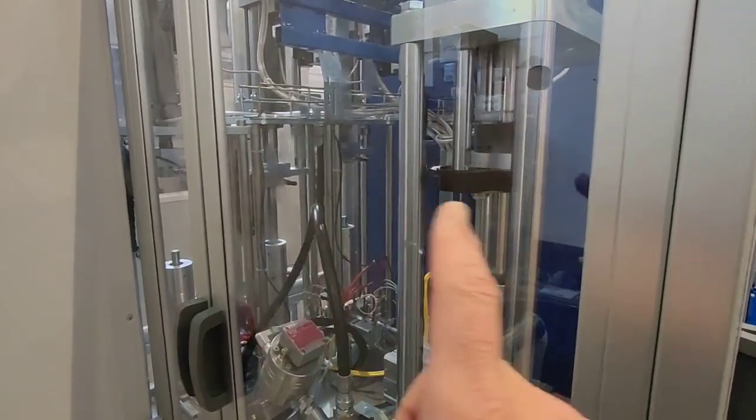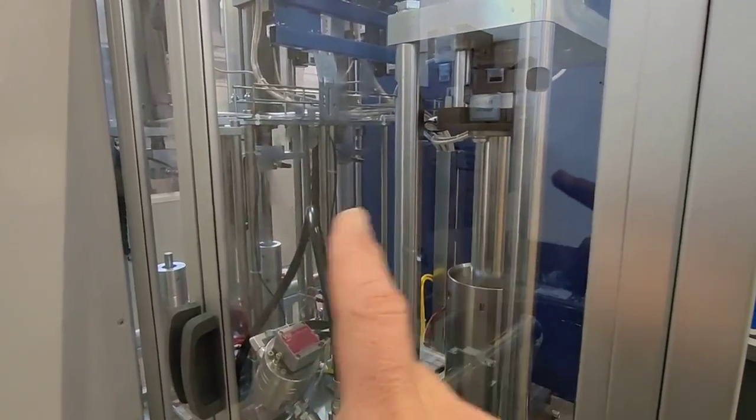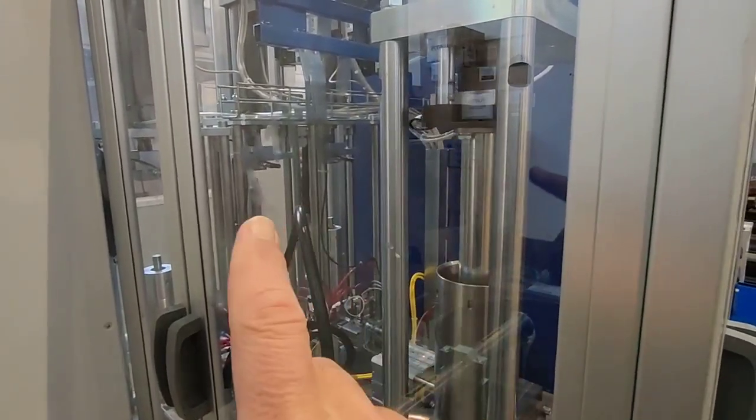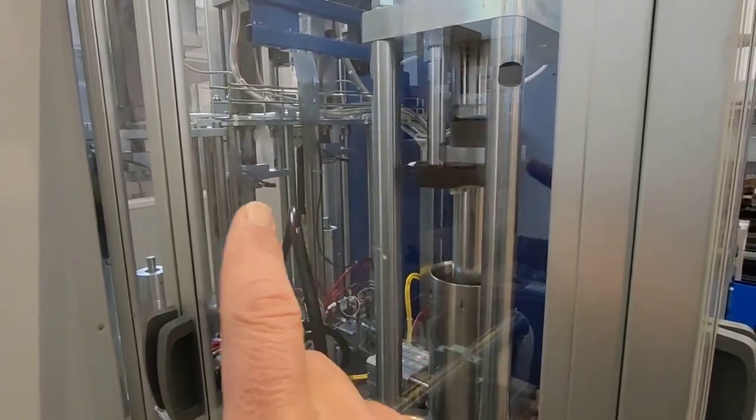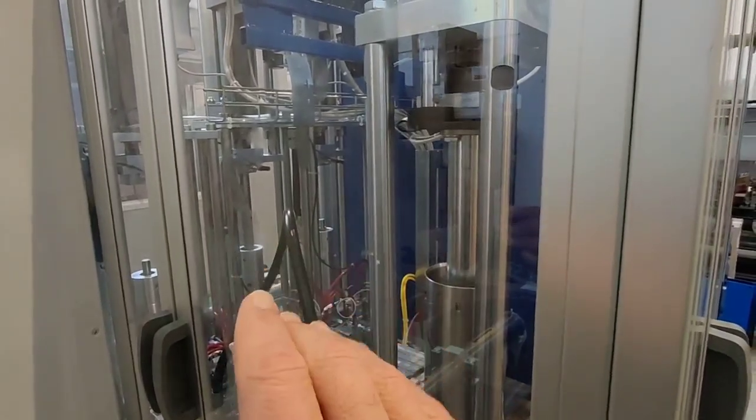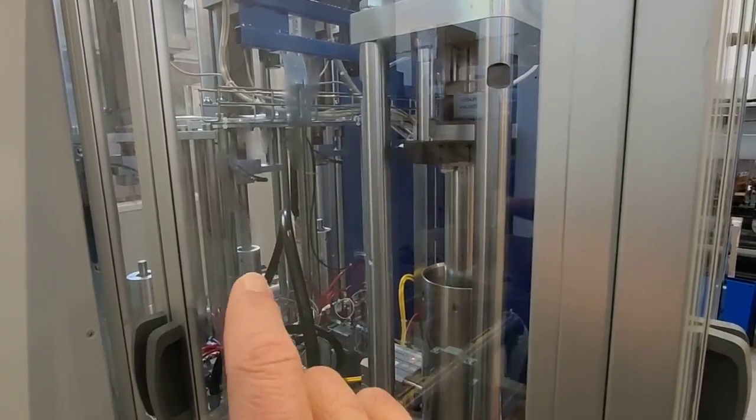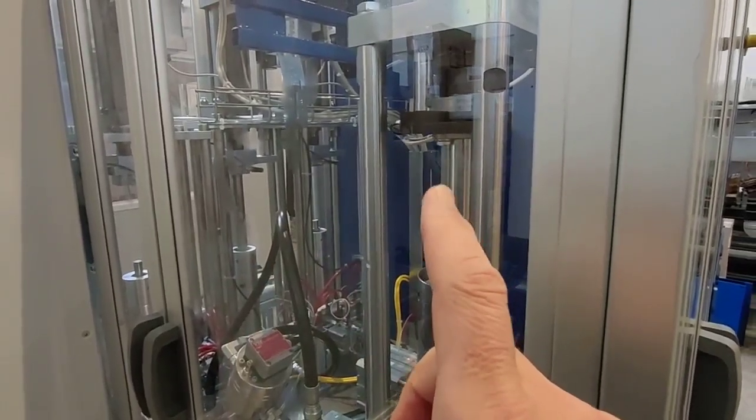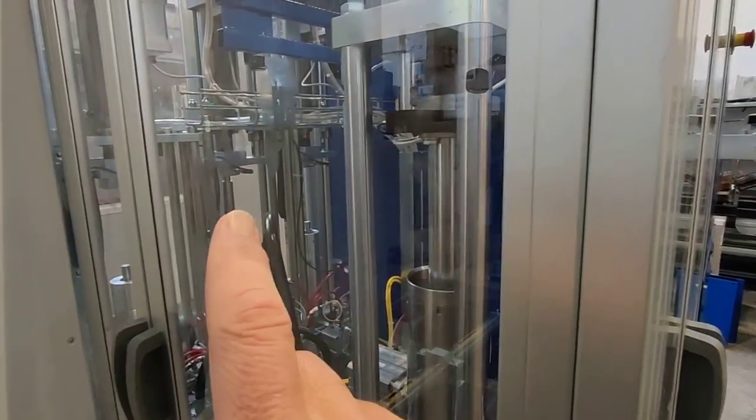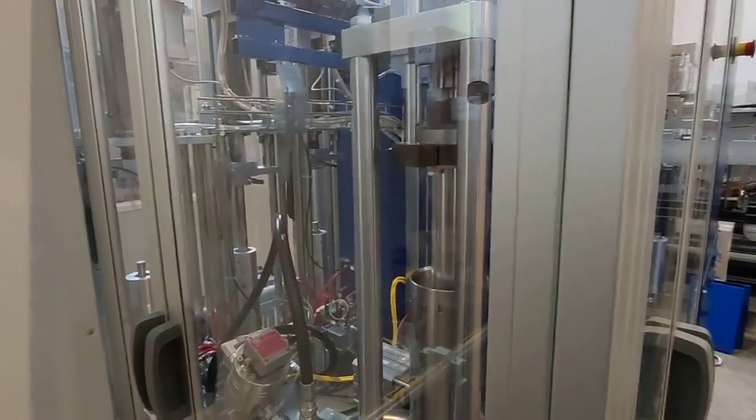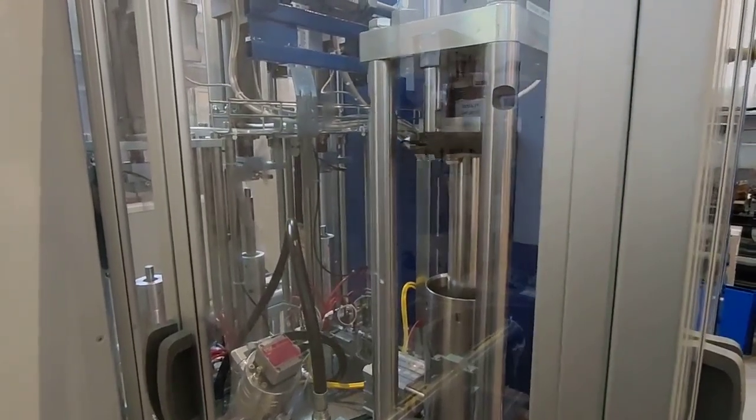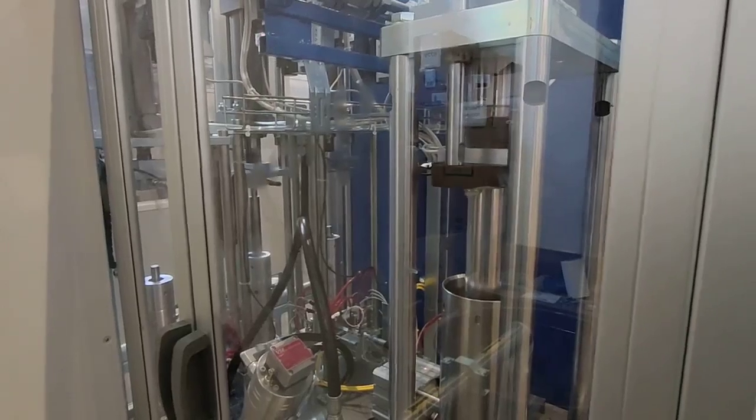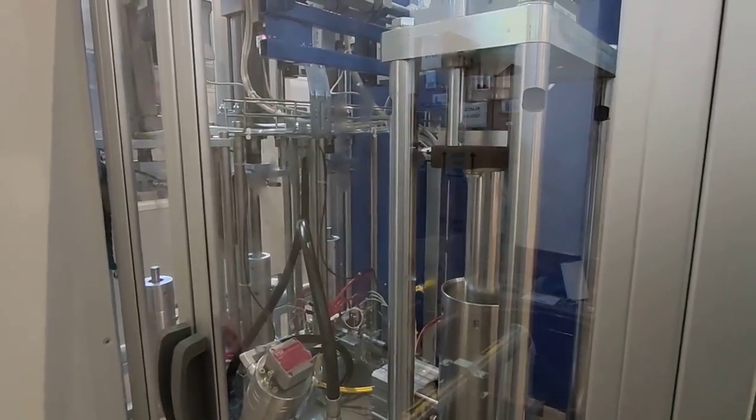As you can see the stroke of the two dosing units are different so that the speed of this one and this one is also different in order to start and to finish the stroke at the same moment. Therefore the speed of this one is faster, the speed of this one is slower, and you can set it by the HMI display depending on the mixing percentage you set up.